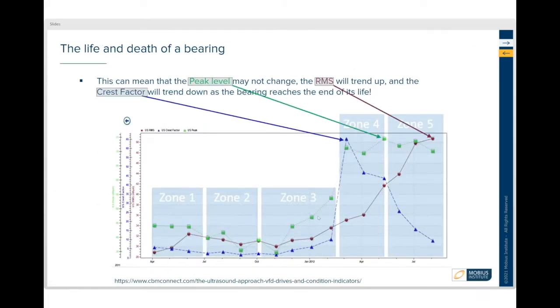We can trend changes by looking at how the RMS changes, how the peak level changes, how the crest factor changes, and not that it's shown here but even how the kurtosis changes, and understand where the bearing is in its life and death process.